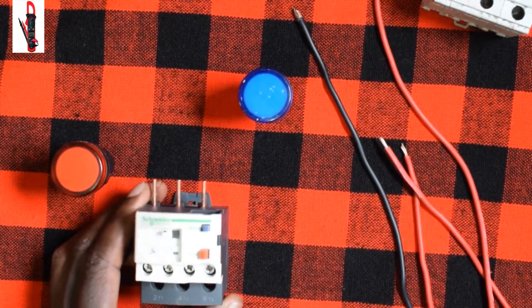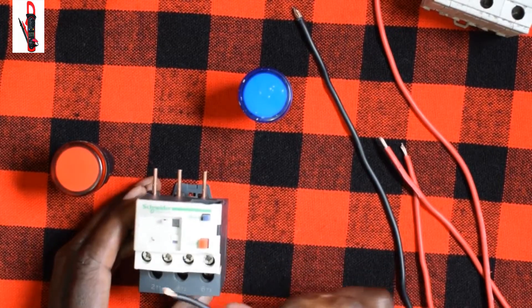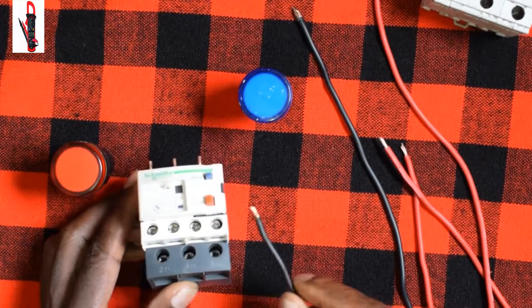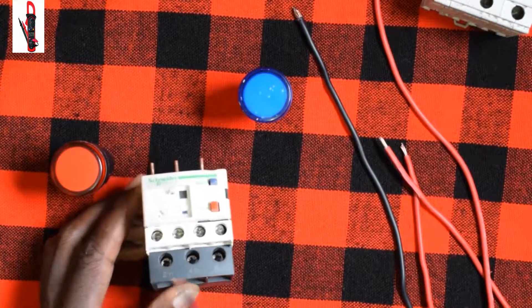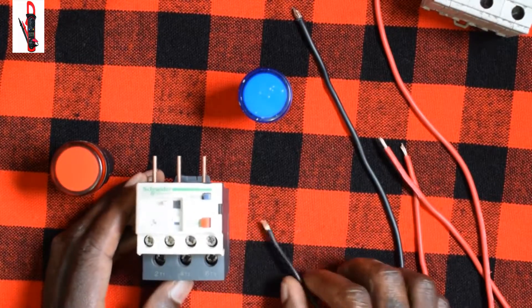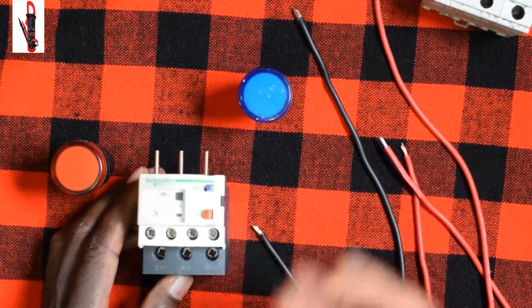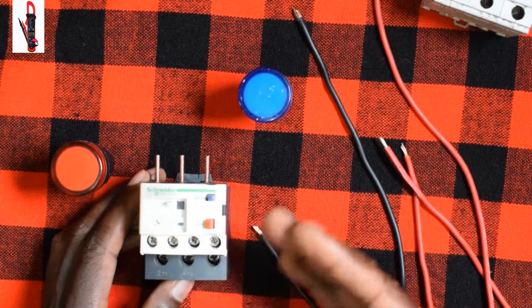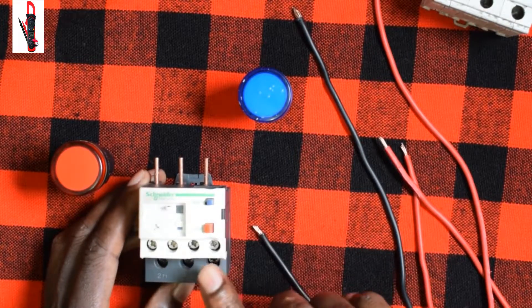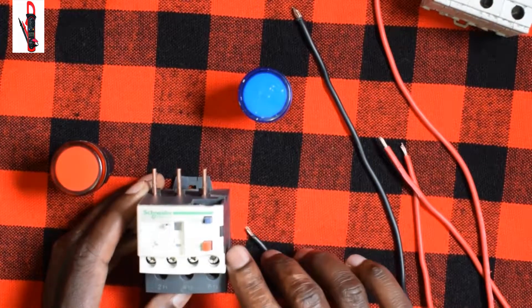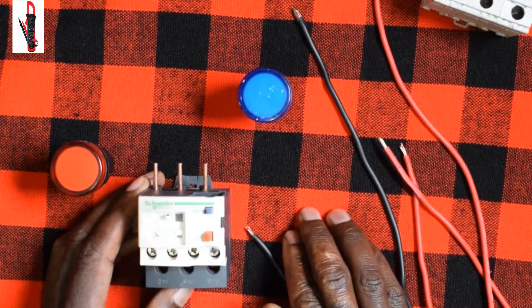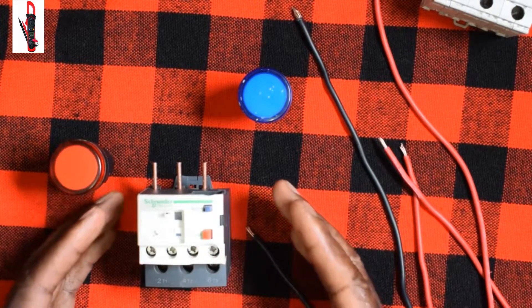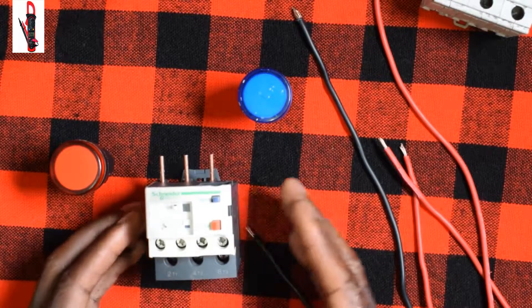First, this overload has some contacts here. You see there are two contacts: NC, that's normally closed, and NO, that's normally open. Initially when we are doing our direct online or we are incorporating an overload in our circuit, we always use the NC - that's the 96 and 95. We use it because if your load, which probably is a single phase or a three phase motor, has a short circuit or the windings are burning, it tends to draw more current.